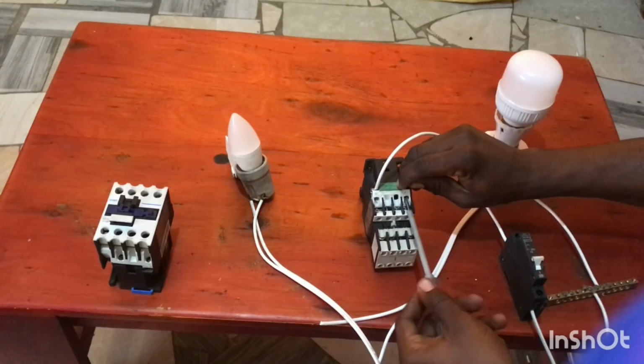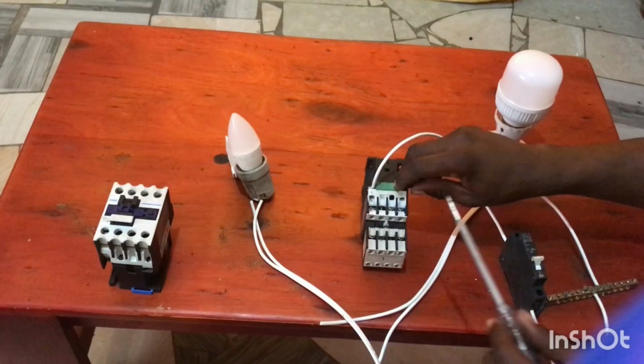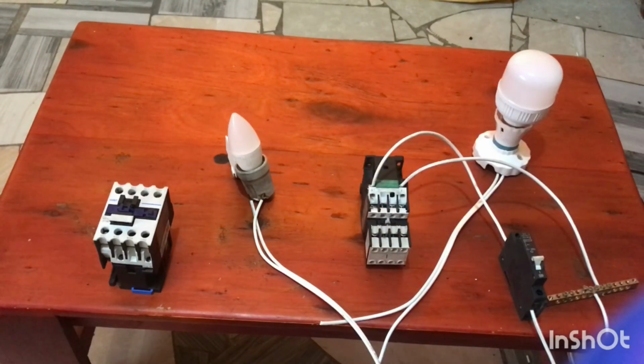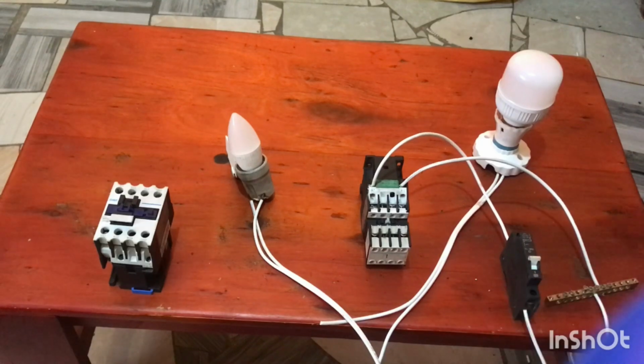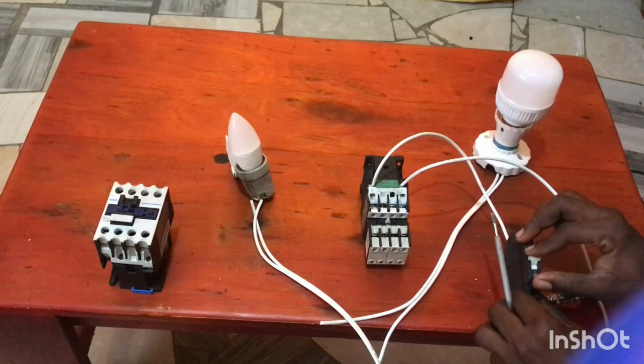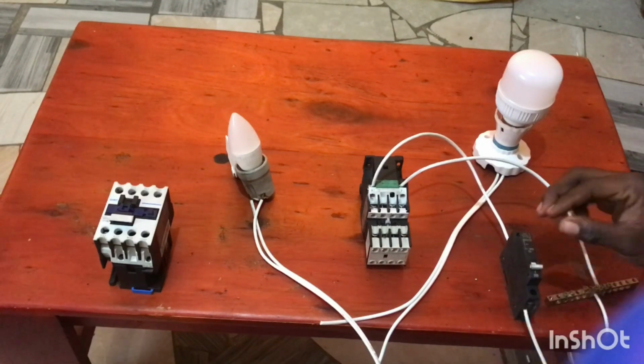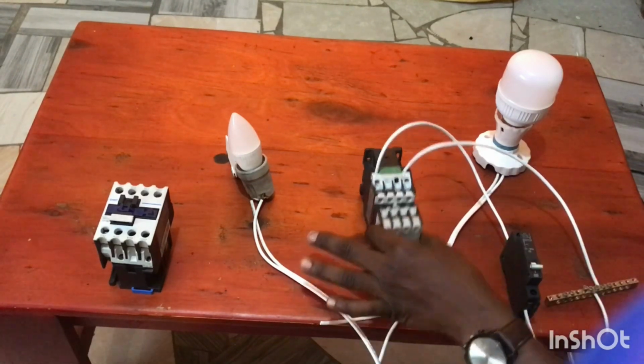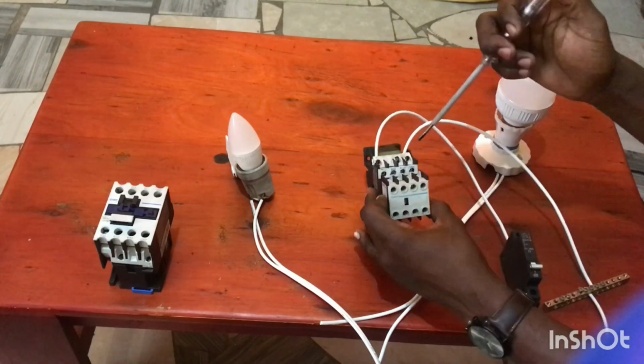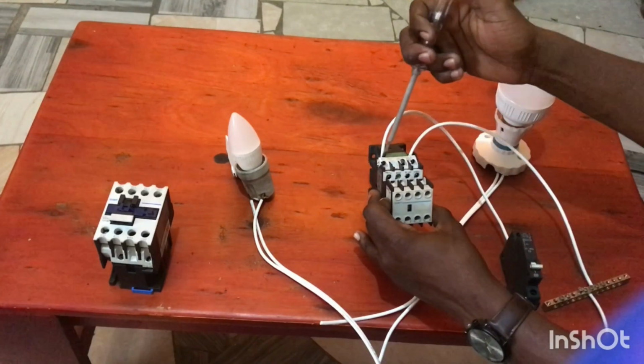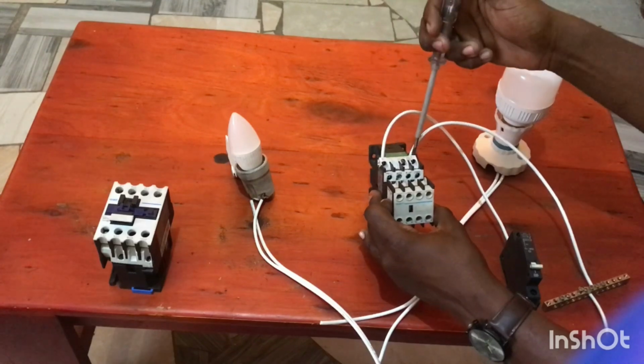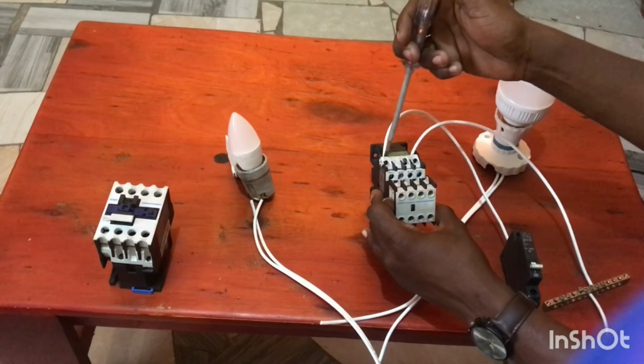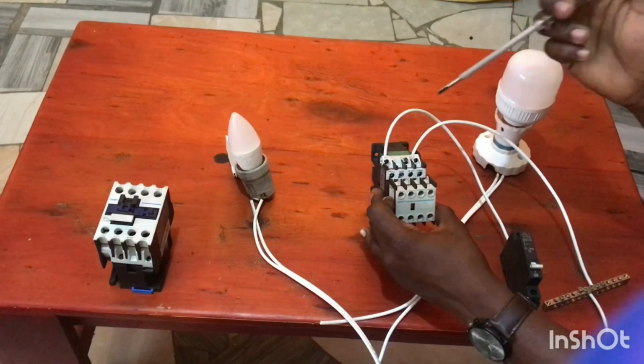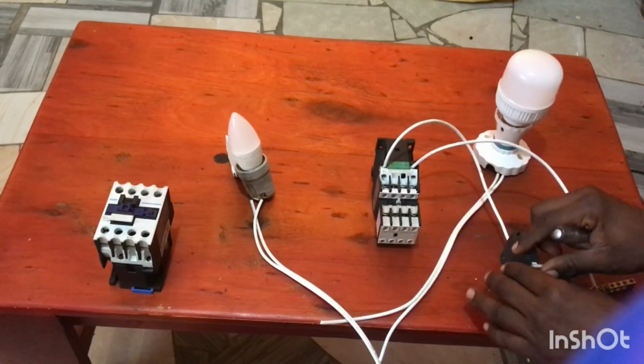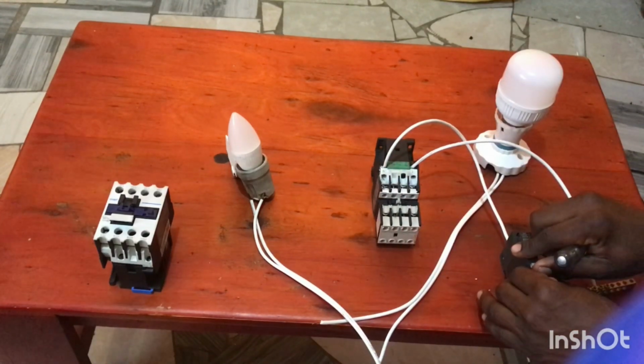Once I switch on the source, this contactor gets energized, and the electromagnetic relays which are inside get excited, or energized. Okay, so this is what happens. As you can see, this contactor is energized. This is A1 and A2, and this is where the power comes from, A1 and A2, positive and negative respectively.